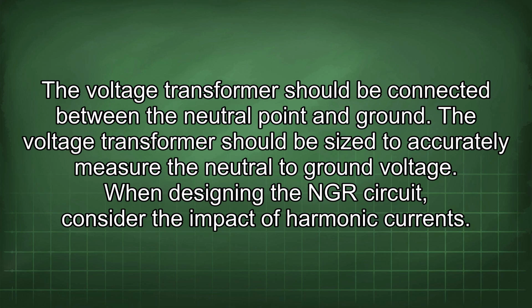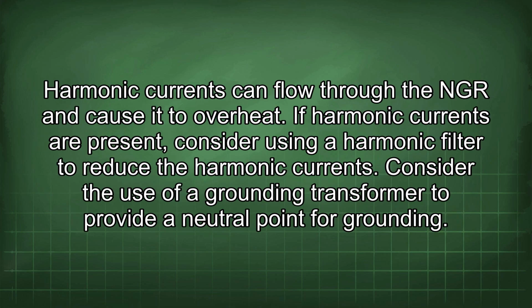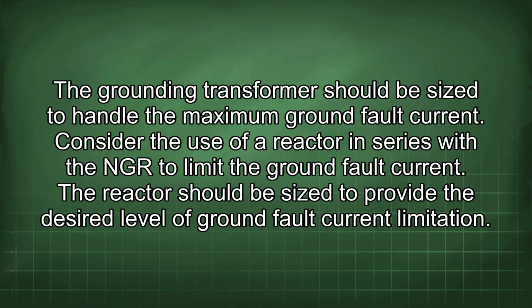When designing the NGR circuit, consider the impact of harmonic currents. Harmonic currents can flow through the NGR and cause it to overheat. If harmonic currents are present, consider using a harmonic filter to reduce the harmonic currents. Consider the use of a grounding transformer to provide a neutral point for grounding. The grounding transformer should be sized to handle the maximum ground fault current.